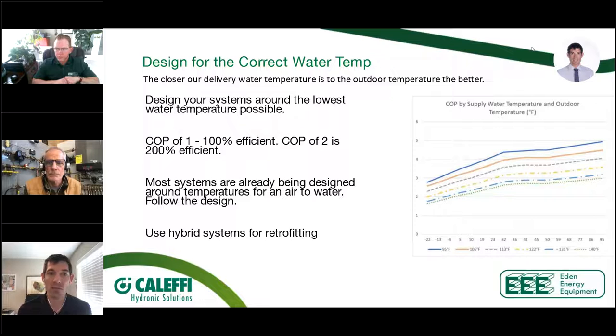A COP of one is just electric resistance heat at that point. And that's the last thing that we want to do, is install a heat pump that's giving you the same return on the energy dollar as an electric resistance element inside of a water heater tank or something like that. We don't want to go down to that number.